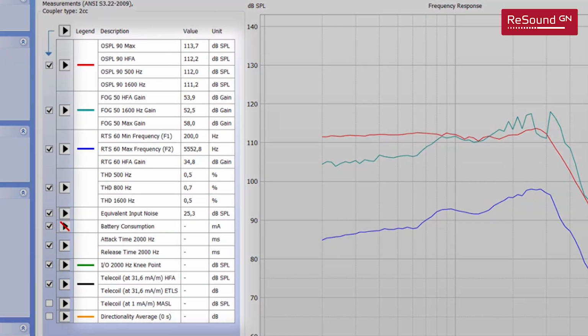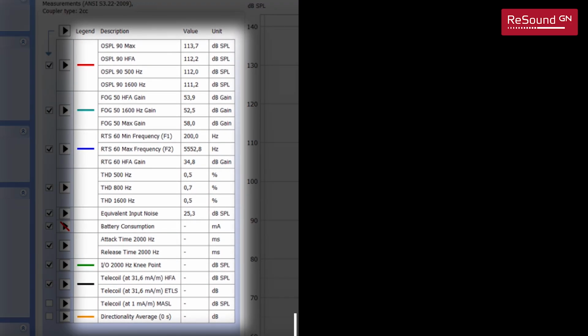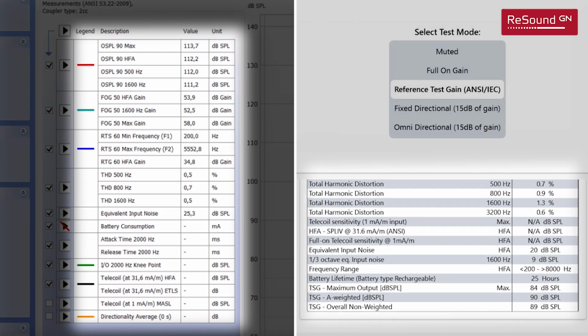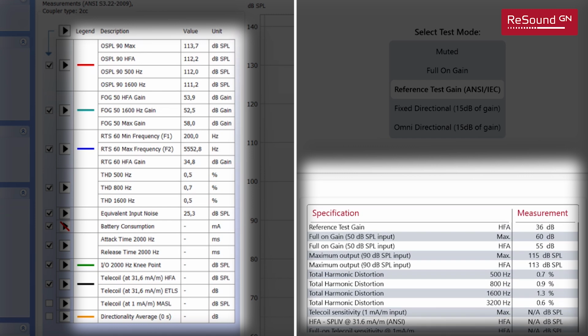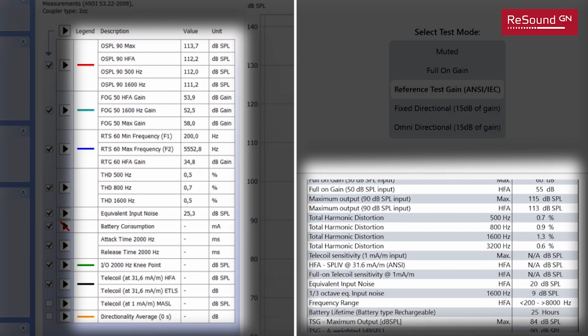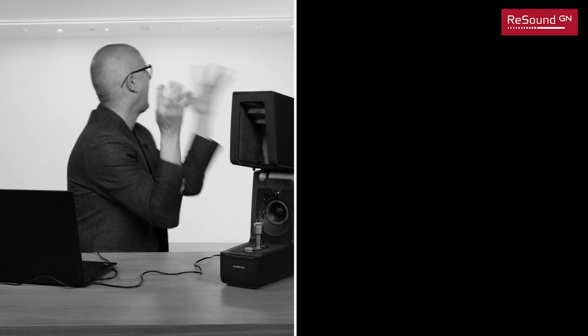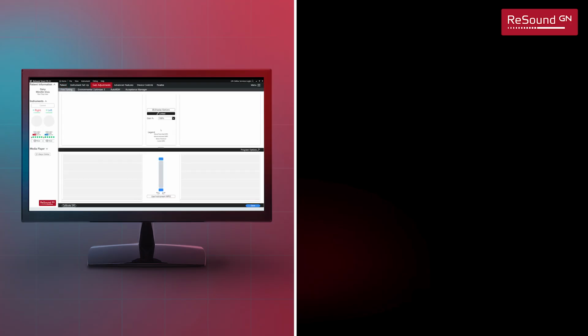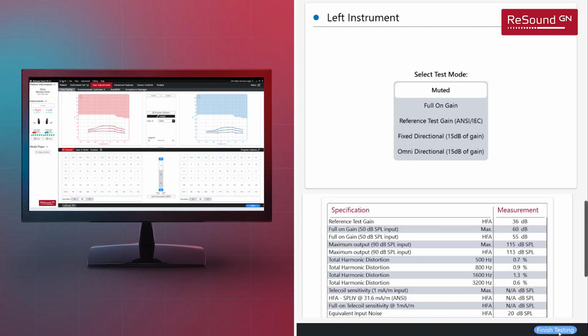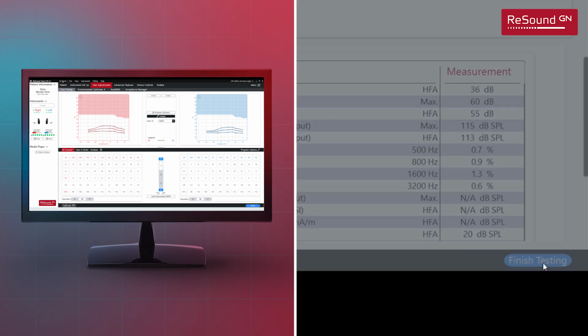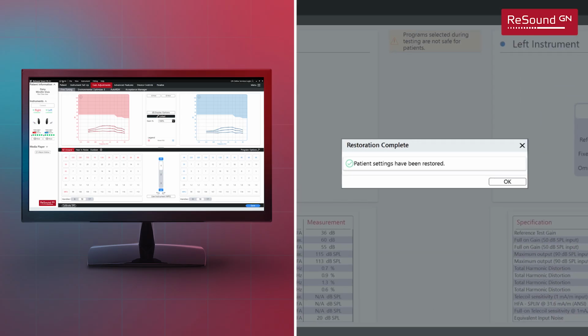And when the test is done, I can easily compare the results of the test box with the specifications of the hearing aids, which are now shown directly in the fitting software. Remember when comparing results that it is okay to have a deviation within 3 decibels. And it gets better. Before, when the test was done, you could not just give the hearing aids to your client because the hearing aids are programmed with full gain and it will blow their ears, which means that you had to reconnect the hearing aids to the fitting software and reprogram them. Now you simply exit the test, and the hearing aids are ready for your client.